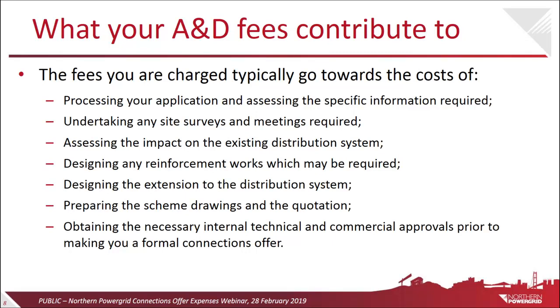What do your fees contribute to? Typically, it's to cover the cost of processing your application, assessing the specific information, undertaking any site surveys and meetings required. We assess the impact on the existing distribution system. We maybe need to design reinforcement of the network, design an extension to the distribution system assets, preparing scheme drawings and quotations, and obtaining all the necessary technical and commercial approvals prior to making that formal connection offer. So there is quite a lot of content of what we actually do that makes up the fees that we charge out.